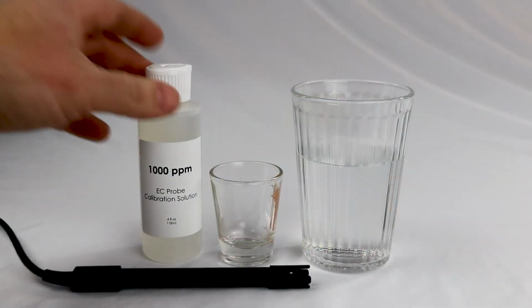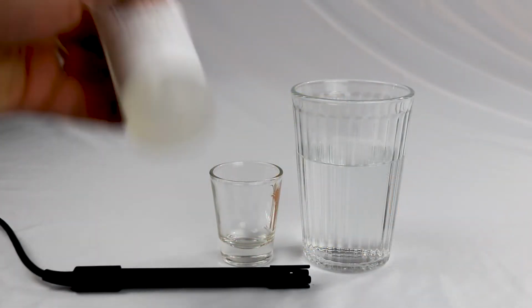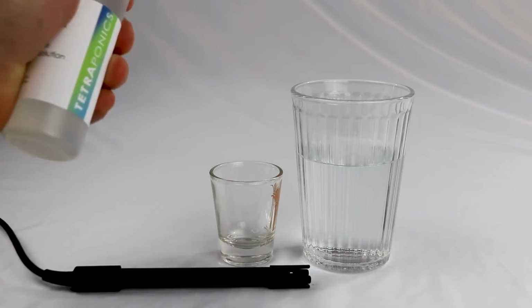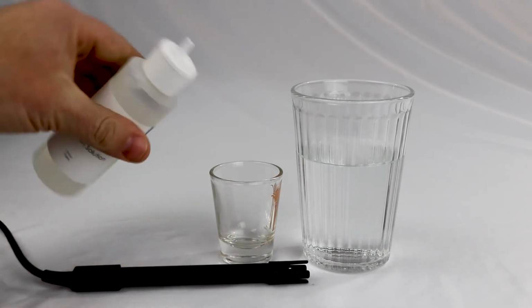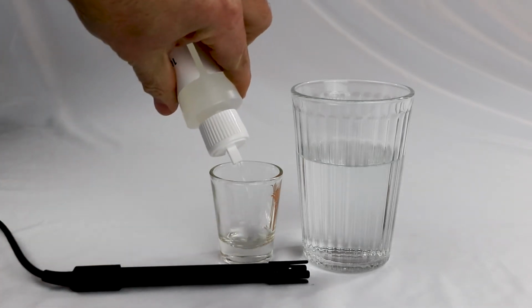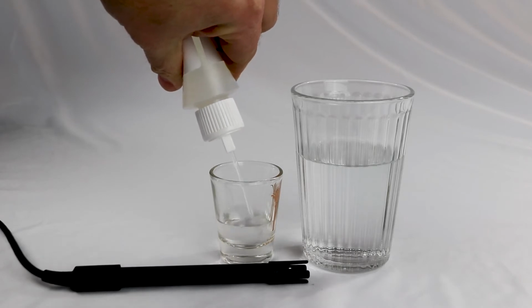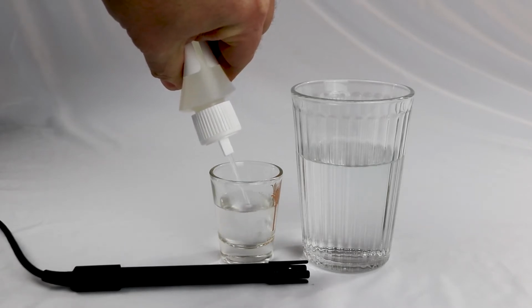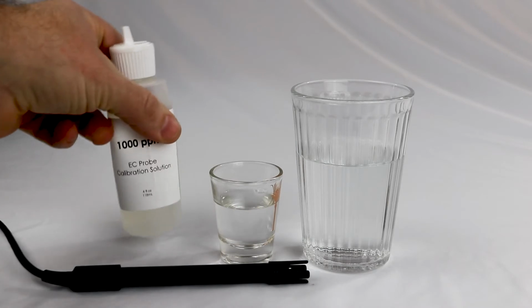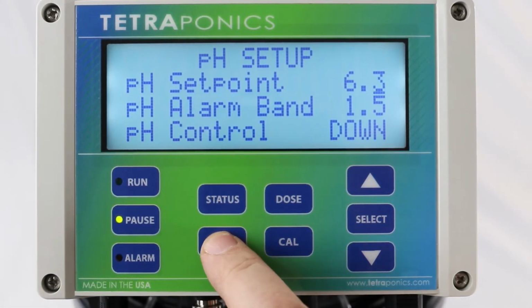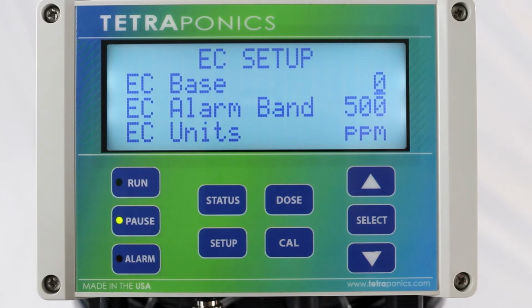Let's start with the EC probe. First, ensure the EC probe and the pH probe are connected to the TETRAPONICS control box. Both probes should be removed from the reservoir and at room temperature. Next, make sure your EC calibration solution is at room temperature and not expired. Ensure your EC base is set to 0 in the EC setup menu.